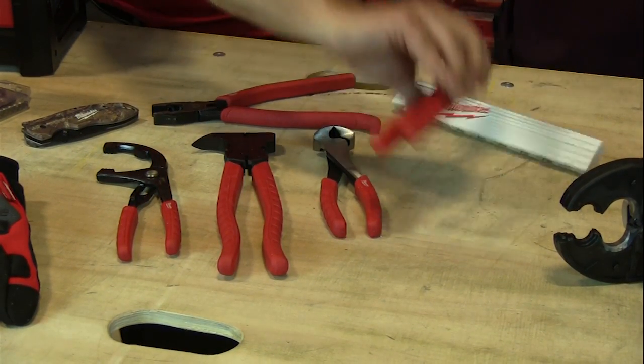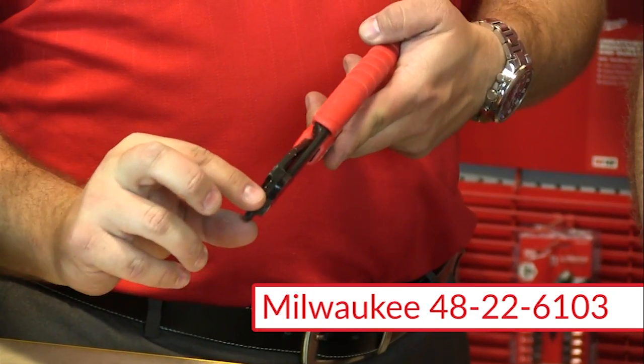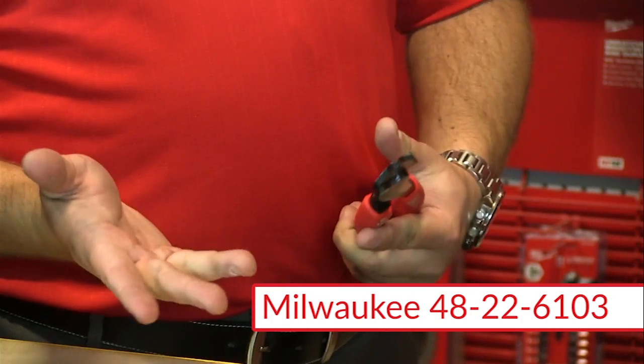So we'll start off with what we call our crimping pliers here. These guys are designed for crimping insulated and non-insulated wire. You've got your basic functions, your crimping and your wire cutting. You can also ream your EMT with this. For those that aren't familiar with that, basically every time you run power line through an EMT tube, you have to make sure you put these guys in there and take off the burrs that tend to form when you cut EMT. That way you're not pinching your line, scratching off the insulation, and potentially causing a fire hazard. So those guys are our crimping pliers.